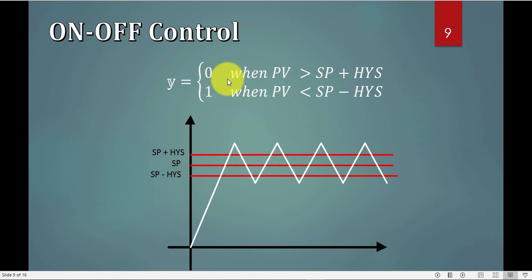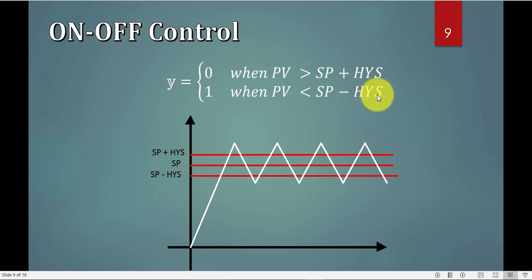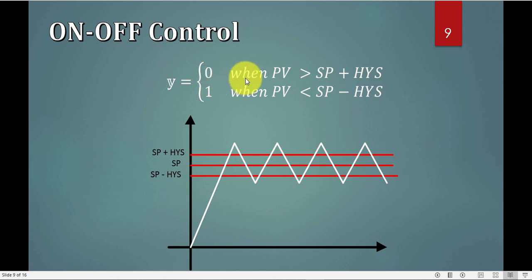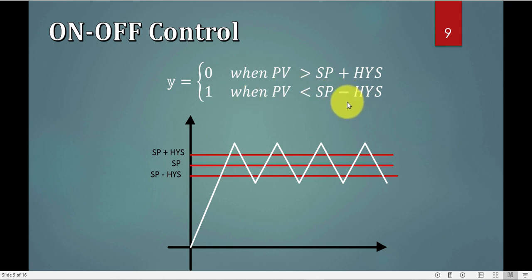Writing the equation is exactly the same thing, my controller will be zero when my PV is higher than set point plus hysteresis, or it is one when my PV is less than set point minus hysteresis, or I can write it as error, it means it is zero when the error is less than negative hysteresis, and it is one when the error is greater than hysteresis.